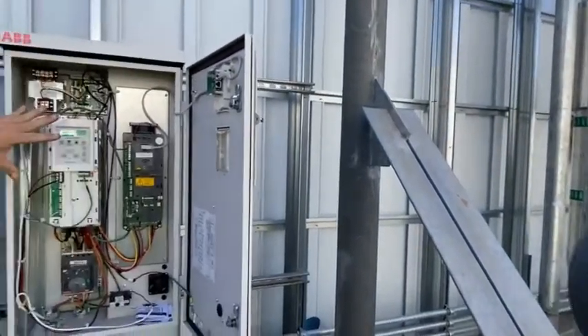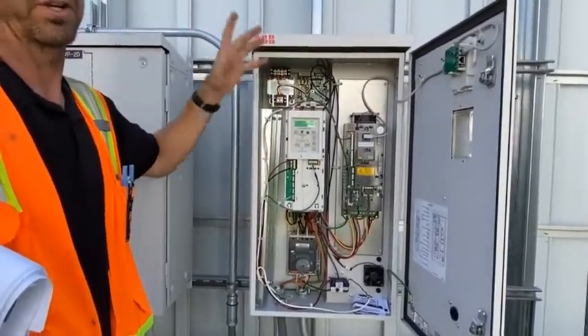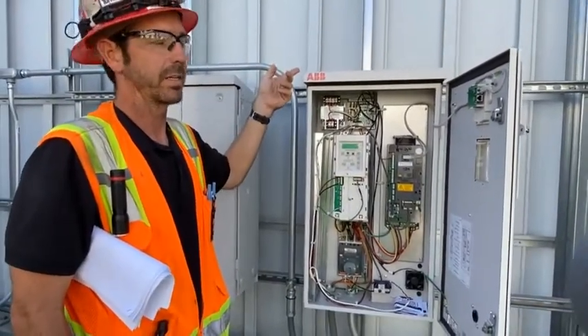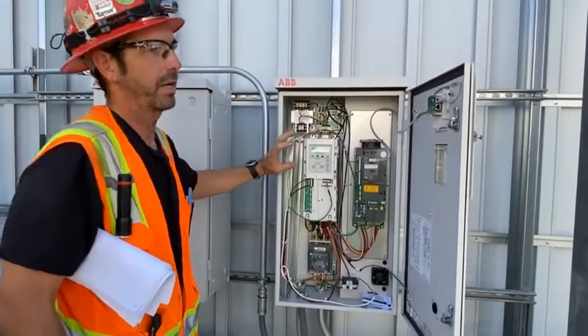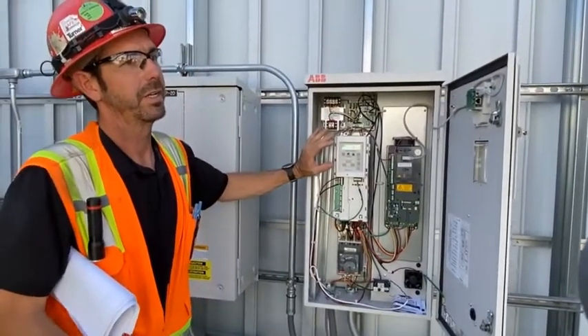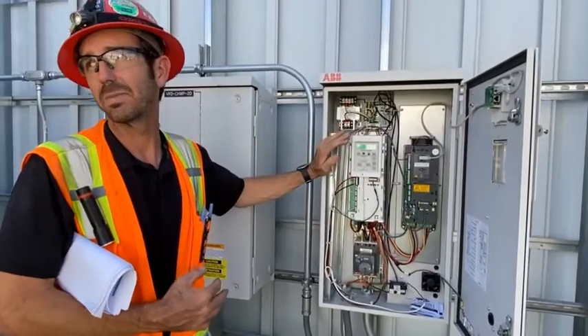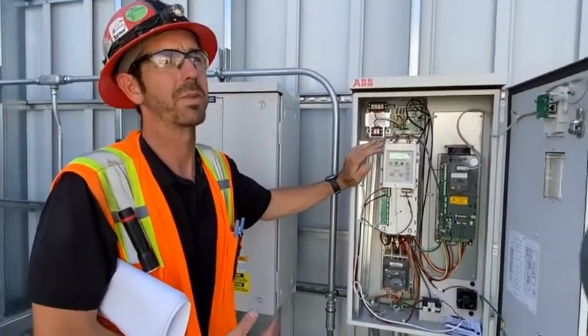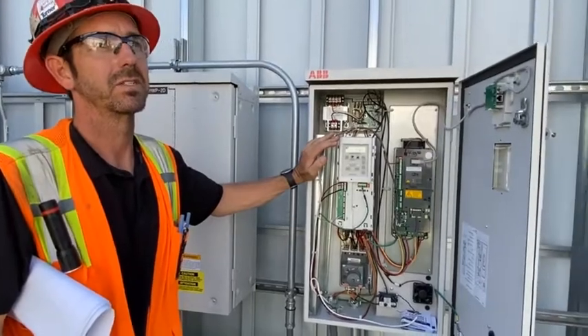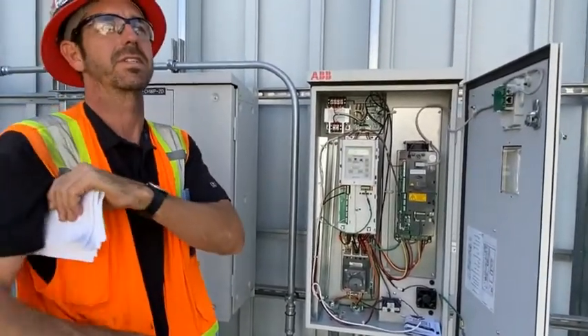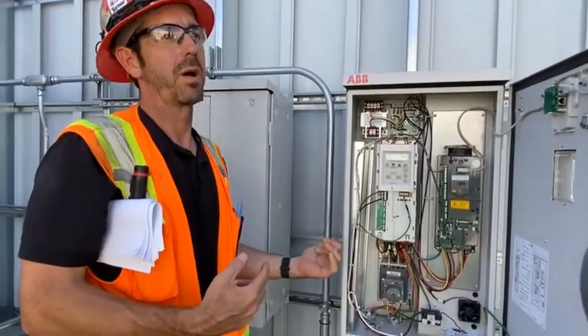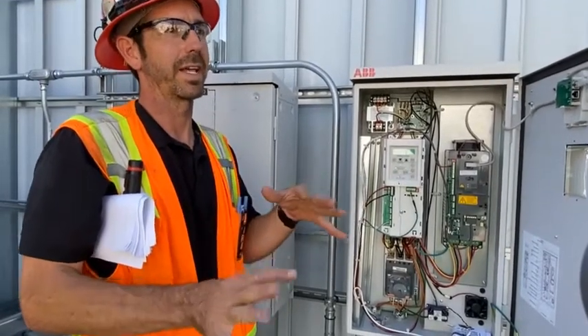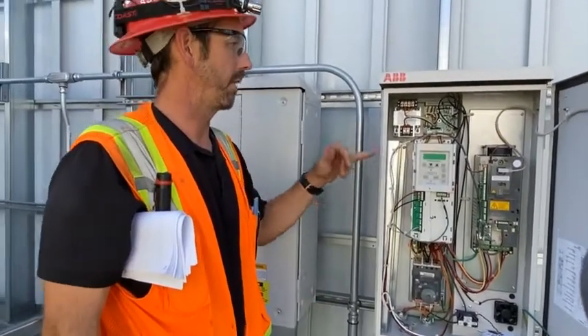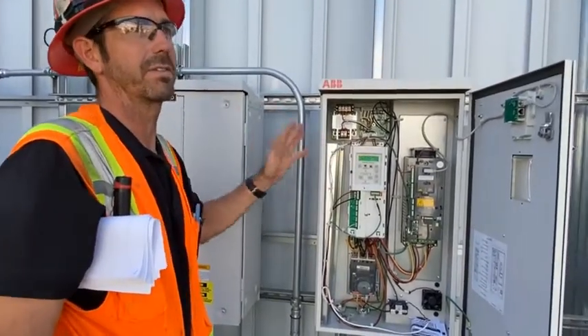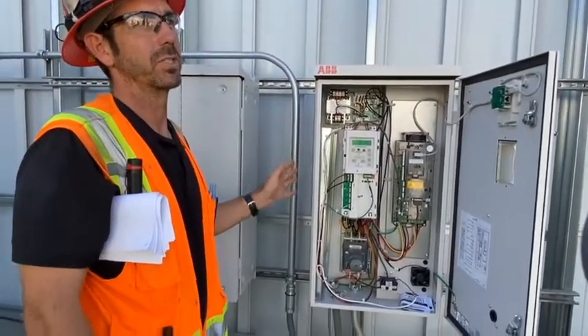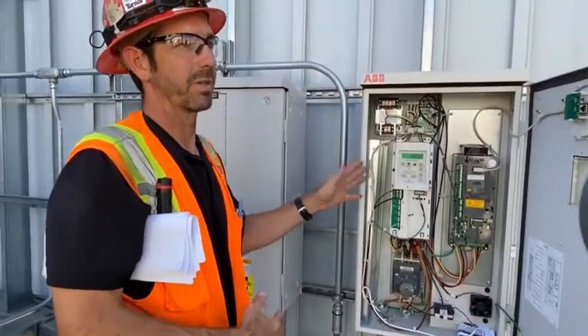On this side over here, we have the bypass. This is what I was talking to you guys about on the other side at the exhaust fan. In this pumping application, we don't want to use the bypass unless absolutely necessary, because the bypass is going to run the pump at full speed, 60 hertz. So if all the air handler valves and the chilled water valves downstairs are closed, you're running this pump at full speed and it's going to kind of deadhead the pump. So only in a major emergency, if you lost both drives on both pumps, should you try to run the bypasses on either one of the pumps.